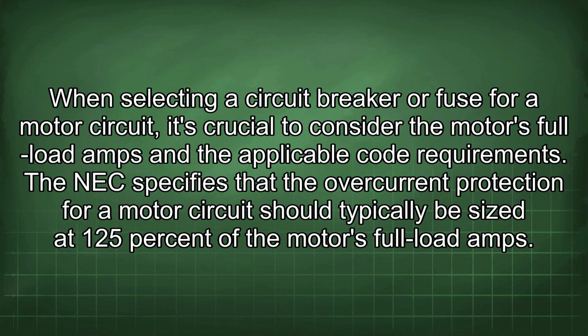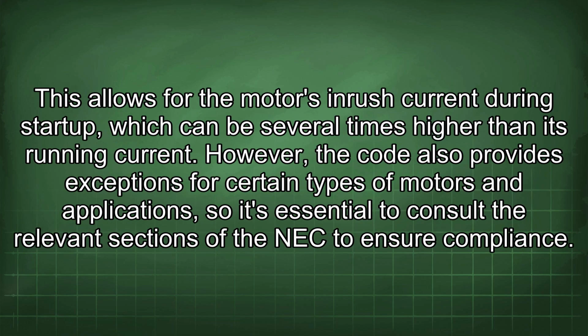When selecting a circuit breaker or fuse for a motor circuit, it's crucial to consider the motor's full load amps and the applicable code requirements. The NEC specifies that the overcurrent protection for a motor circuit should typically be sized at 125% of the motor's full load amps. This allows for the motor's inrush current during startup, which can be several times higher than its running current.